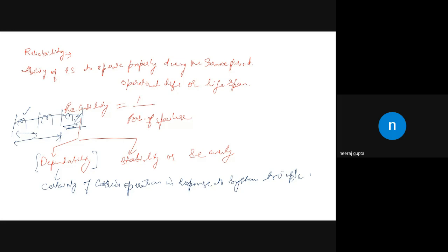So dependability is the degree of certainty that the relay will operate correctly. If we quantify it, dependability equals the number of correct trips divided by the number of desired trips, multiplied by 100. Dependability can be improved by increasing the sensitivity of the relaying system. That is, the relay must be sensitive to the task for which it is intended.